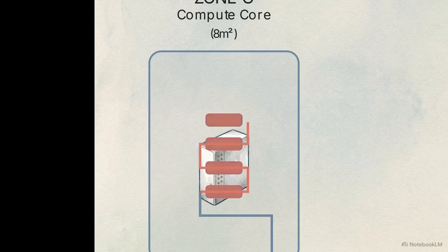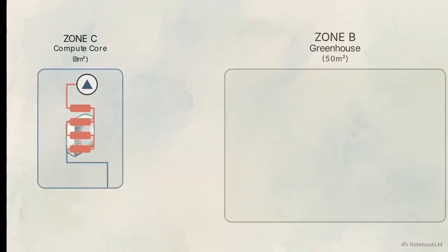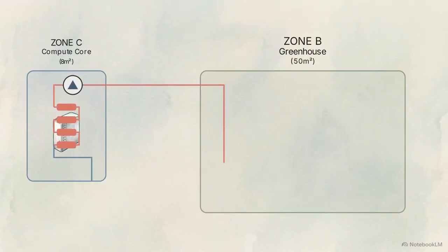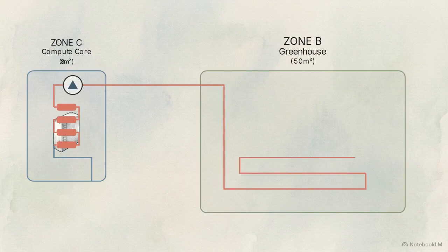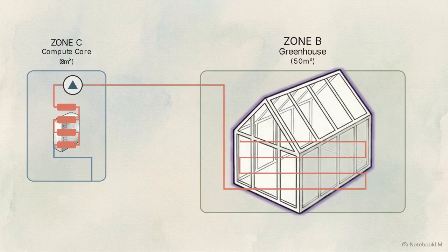Coolant lines physically attach to the processor nodes, absorbing thermal energy directly from the silicon and turning hot as they exit the chassis. Instead of venting this hot liquid into the atmosphere, pumps push it out of the secure server vault. The schematic shows those red lines routing directly into Zone B, a 50 square meter luxury glass greenhouse, where the heat radiates outward into the enclosed space.